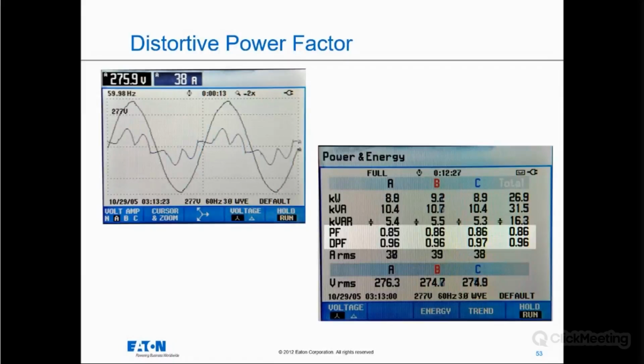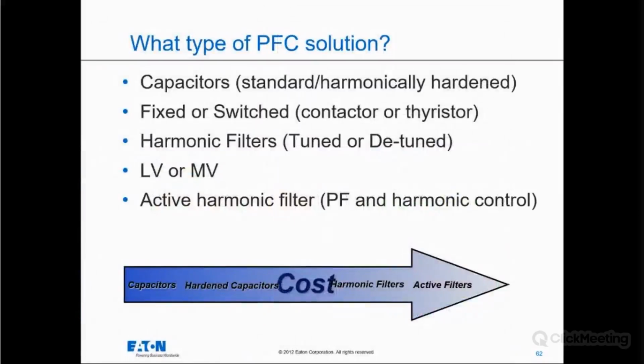So there's different types of equipment. If I have harmonics, does that mean I can't use capacitors? If you have harmonics and poor displacement power factor, yes, you can actually add what is known as a filtered product to deal with the harmonic situation in your building, and/or add, as we discussed, harmonic correction units to also address if you have tremendous amounts of harmonics in your facility.